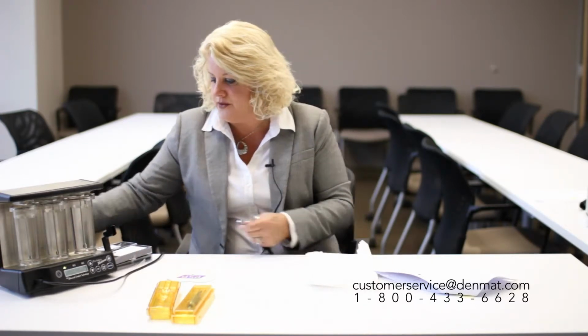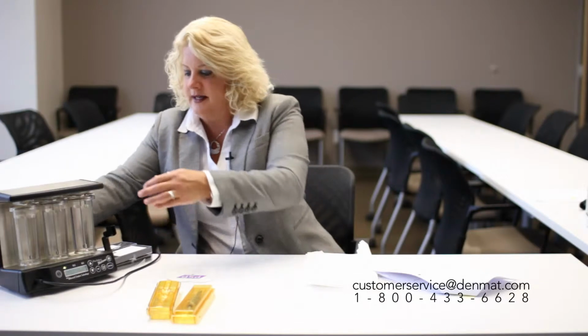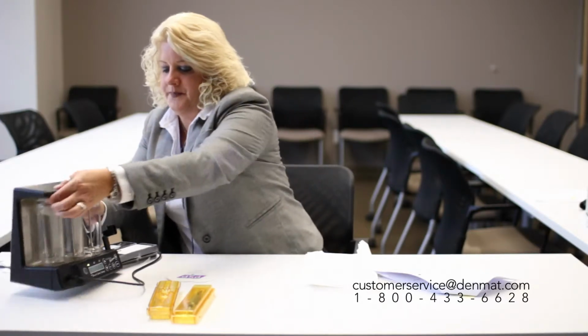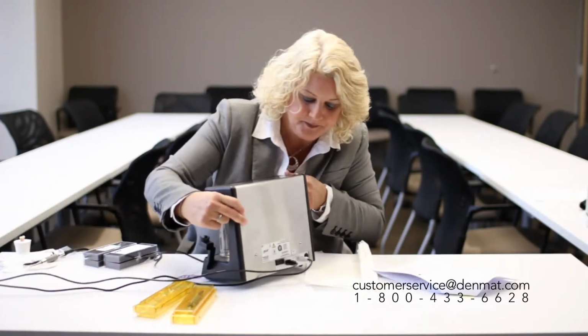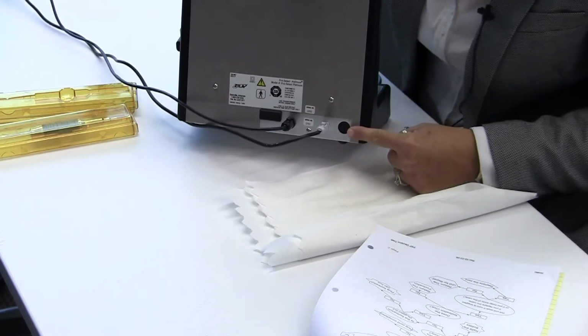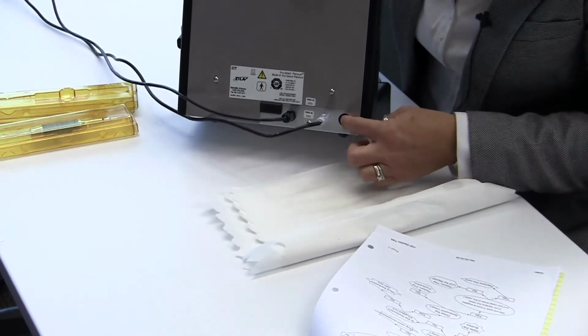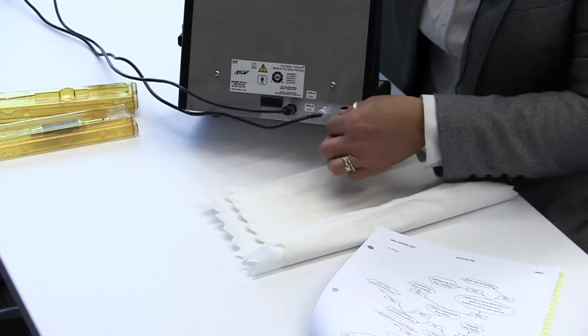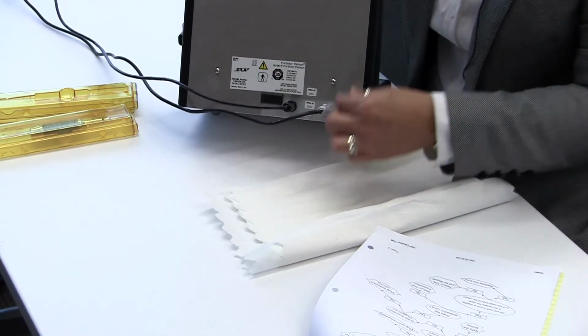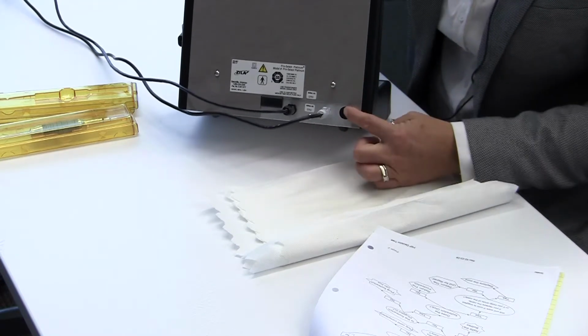So here's the instance where we're now going to move on to if the unit itself will not power up. If the unit itself will not power up, there is an area, and I will turn this unit around so that you can see. There is an area in the back where there is a fuse. Here is where the fuse is located. So what you're going to do is take a screwdriver and you're going to be able to unscrew it, and the fuse will be included in this black piece here.